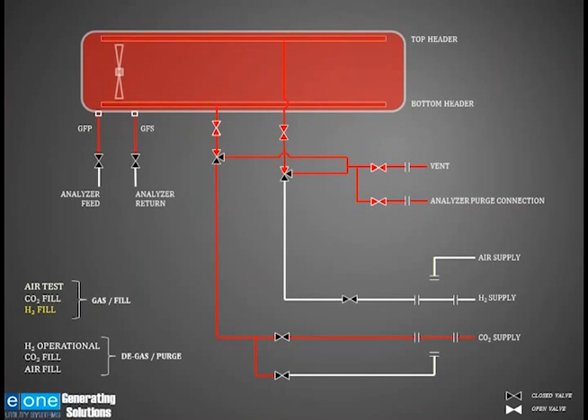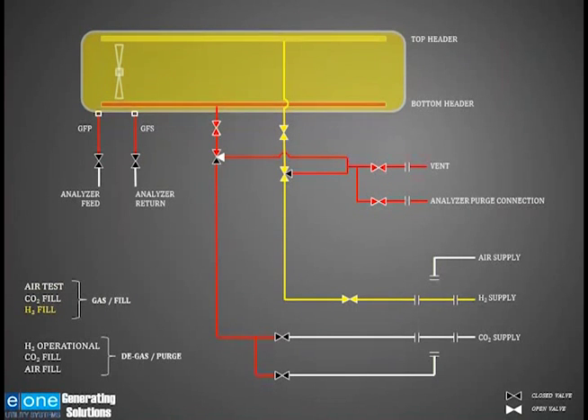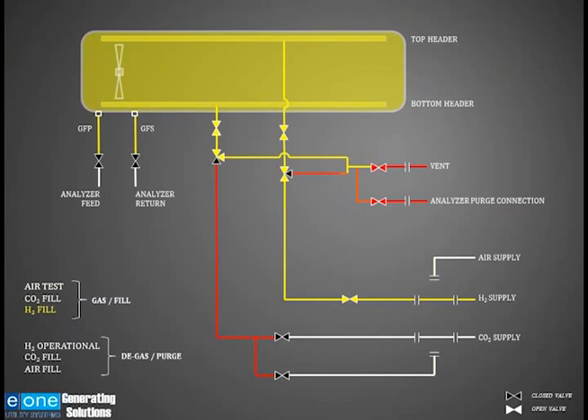So I'm going to now disconnect my CO2 line and start opening the valves for my hydrogen feed. The hydrogen is going to come in through the top header. The hydrogen being a light gas is going to go into the top header, and it's going to force the heavier CO2 out the bottom header. And again, you can note that the analyzer on the analyzer purge connection is not going to see hydrogen until the generator is filled with hydrogen.